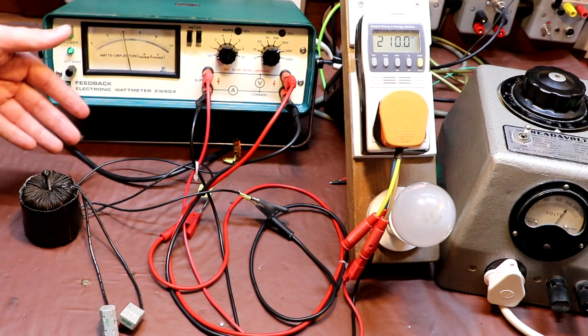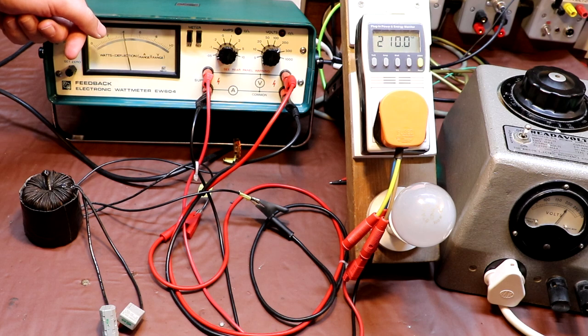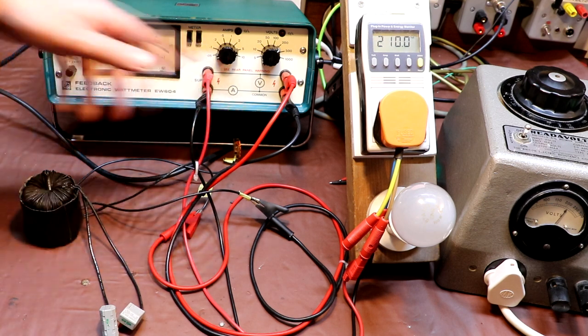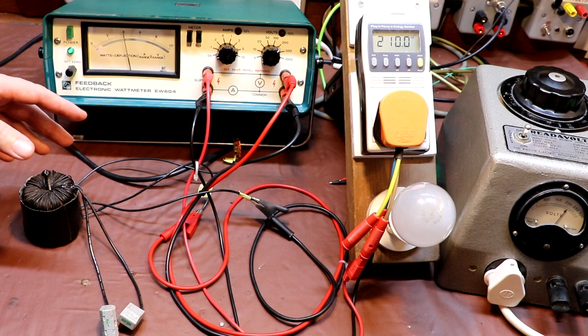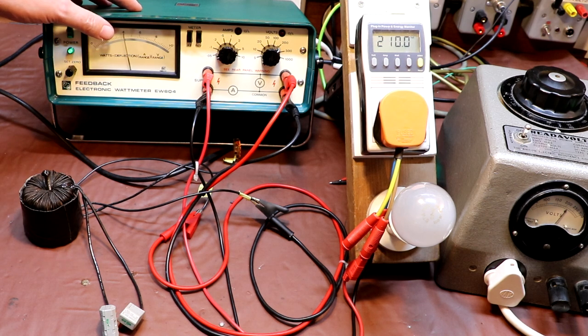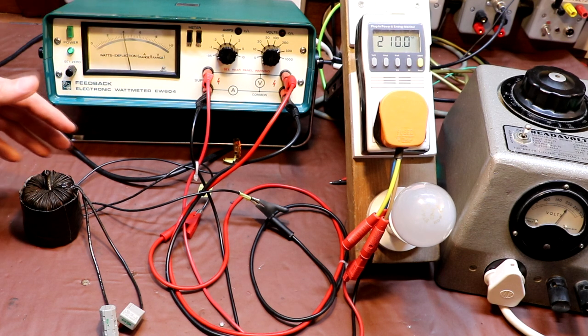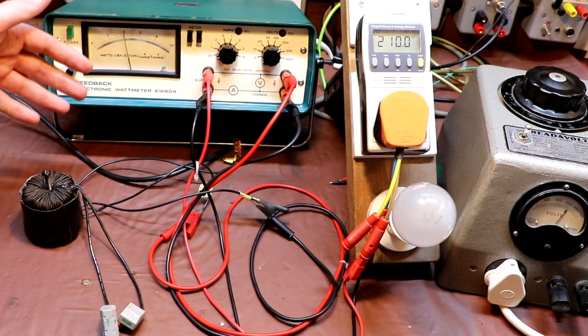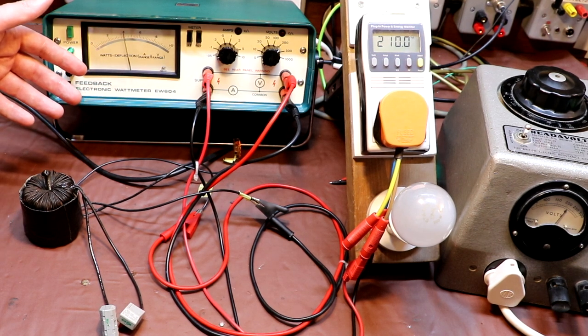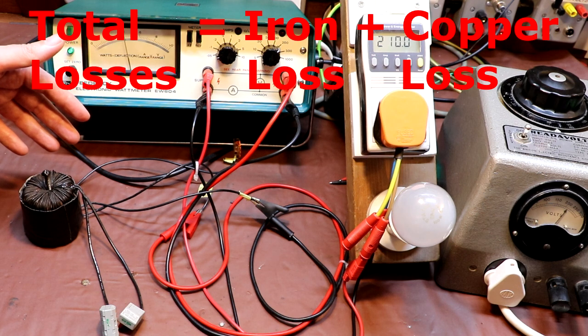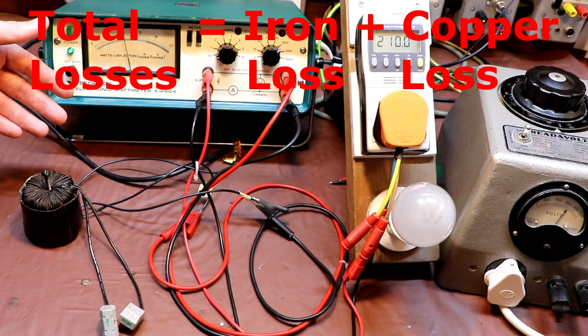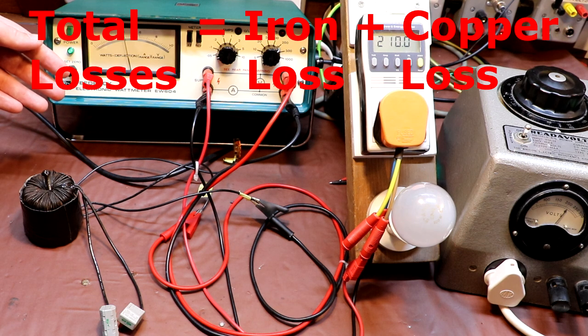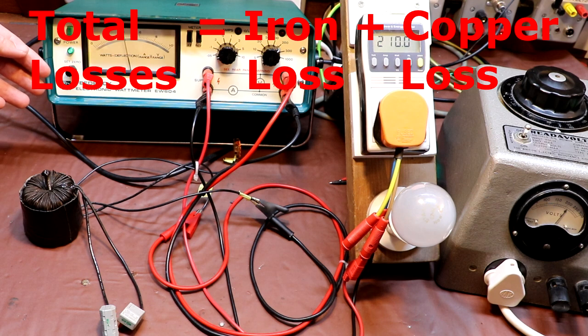So the total core loss is the 4 watts. Now a few moments ago we measured the overall loss within the transformer system, and we only measured 4.2 watts of loss, and that would have been iron and copper losses combined. So the fact we've just measured our iron losses as 4 watts would probably predict that our copper losses should be around 0.2 if they're to add up together, which in theory they should do. So let's now conduct the slightly more interesting short circuit test.